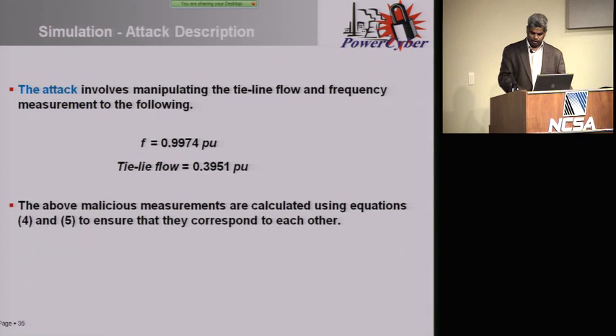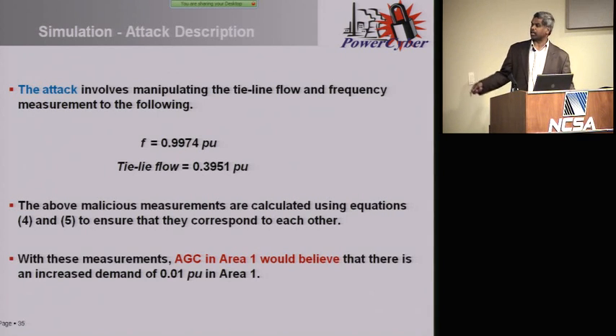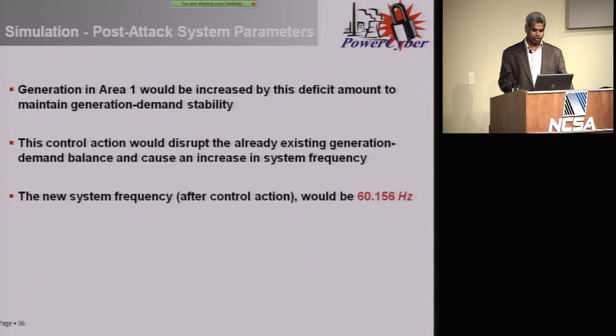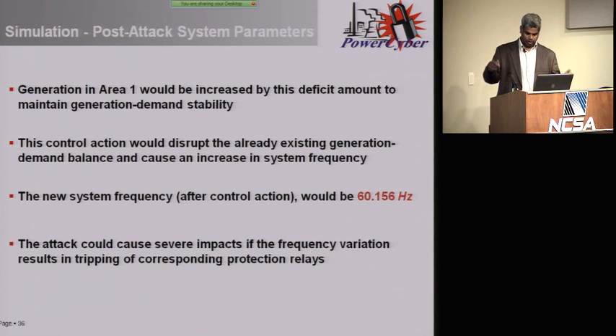This would make the AGC in the control area think it needs to increase generation. So it will increase generation, causing the overall net frequency of the system to go from 60 to 60.156, which is well beyond the acceptable limit of NERC guidance. This can cause frequency oscillation, violating frequency characteristics, which can lead to other actions.